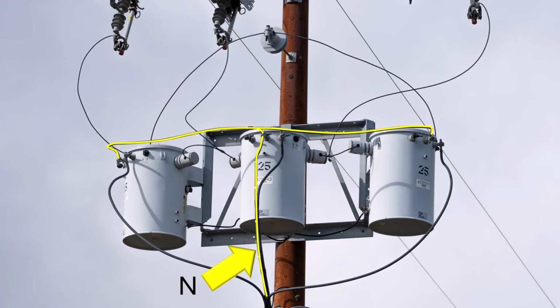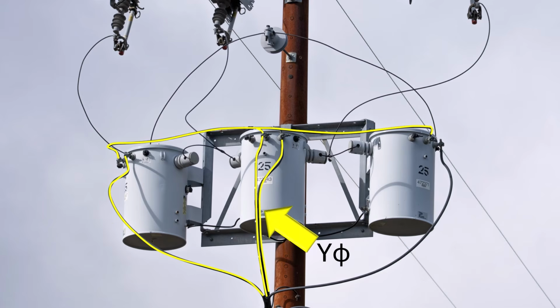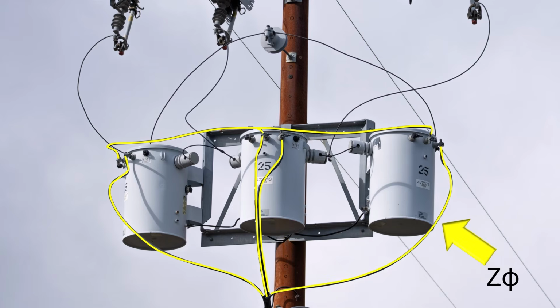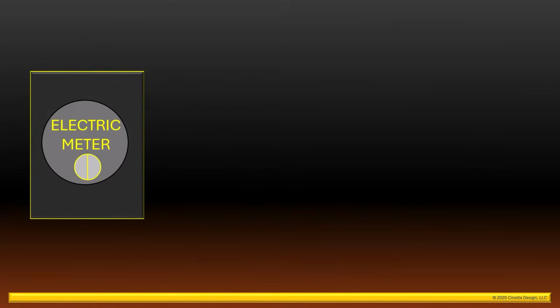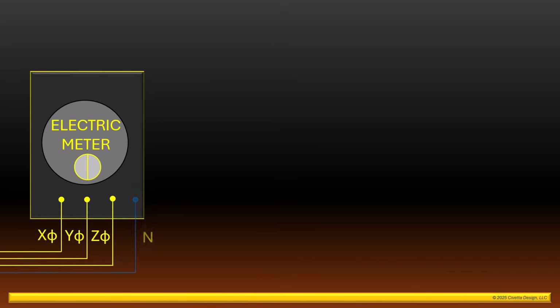The X phase lead wire is connected to the right side bushing of the transformer on the left. The Y phase lead wire is also connected to the right side bushing of the middle transformer. And the Z phase lead wire is connected to the right side bushing of the transformer on the right. These four conductors make up the three-phase, four-wire service connected to the customer's meter panel. The four conductors are attached to the customer's meter panel: X phase, Y phase, Z phase, and the neutral.